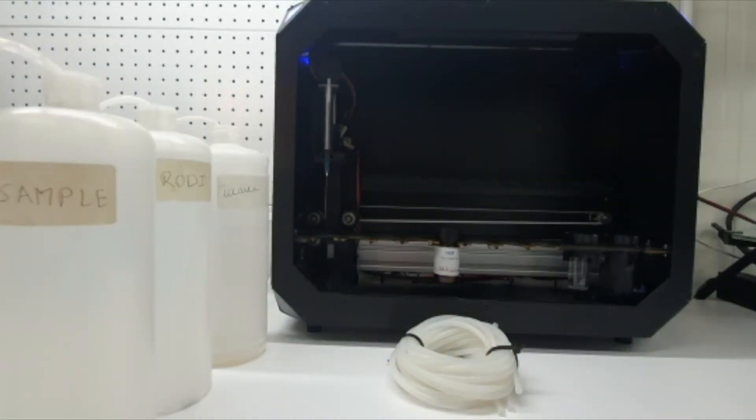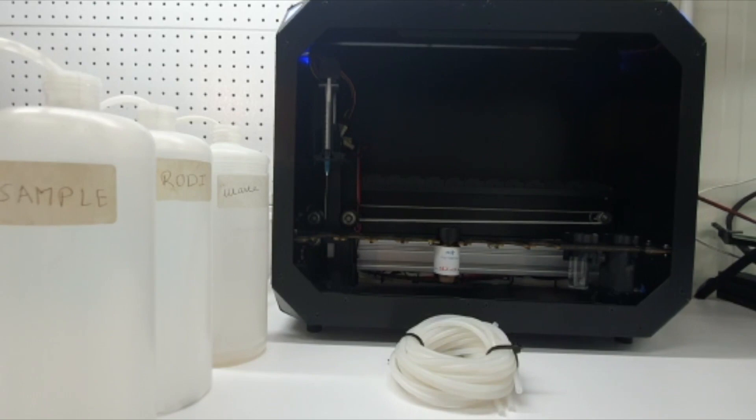These are the air bubbles we are referring to. Air bubbles can be caused by either elongating the silicon sample tube, which is about two meters, or the silicon sample tube is not well immersed in your tank.